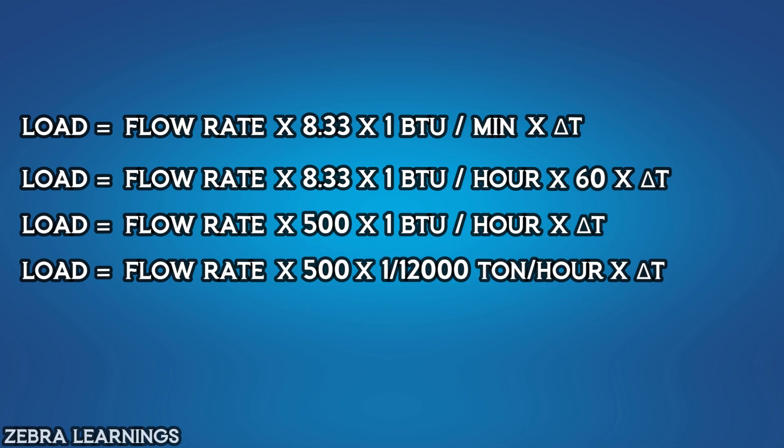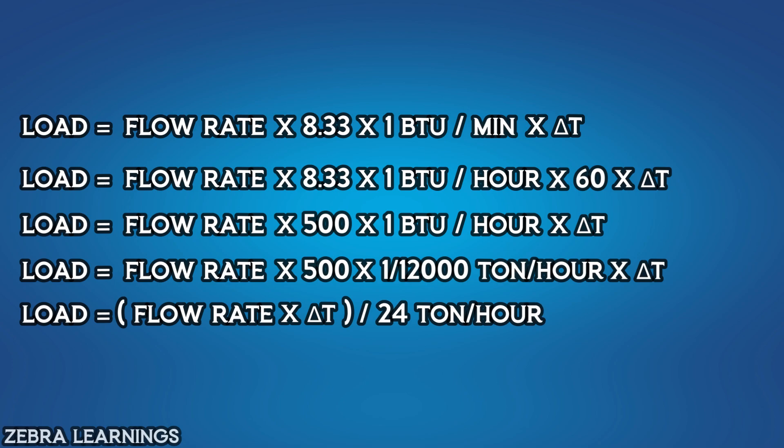So the final formula is load equals flow rate multiply delta T overall divided by 24, ton per hour. This is the simplified formula for calculating chiller load.